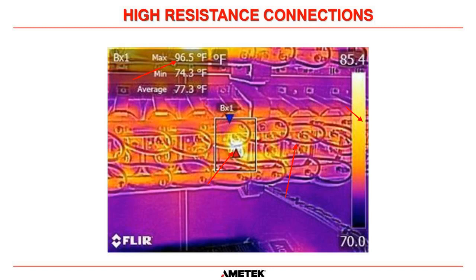So it was still making connection, but it was a high resistance connection. And you say, well, it was still in circuit, so what's the problem? Well, that heat is a problem. It's going to eventually damage the insulation of the cable. That heat is going to migrate into the capacitor, and we'll find out a little bit later that heat is the number one enemy of capacitors. It causes the capacitor to lose life. So that heat would have prevented the capacitor from reaching full life and would have caused a premature failure.